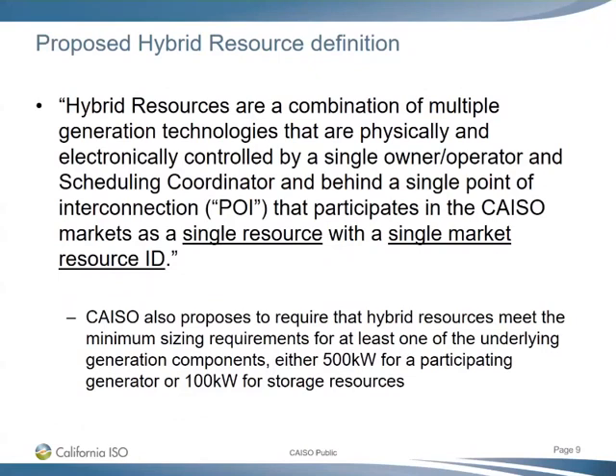Susan Schneider from Phoenix Consulting asked whether the 500 kW could be the combined total of storage and generation, or if generation itself must be at least 500 kW. Chris clarified: the intent is that either of the underlying components individually meets its minimum sizing requirement. So for a storage-and-solar hybrid, either the storage must meet 100 kW or the solar must meet 500 kW — not combined. Each component is assessed against its own threshold independently.